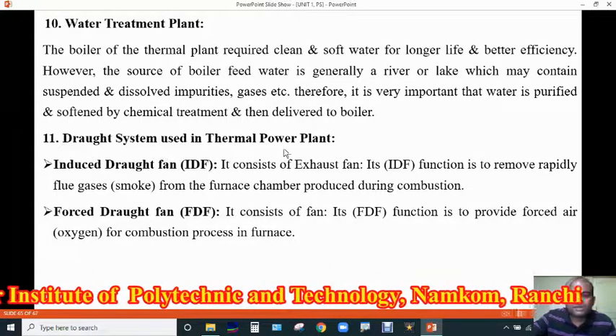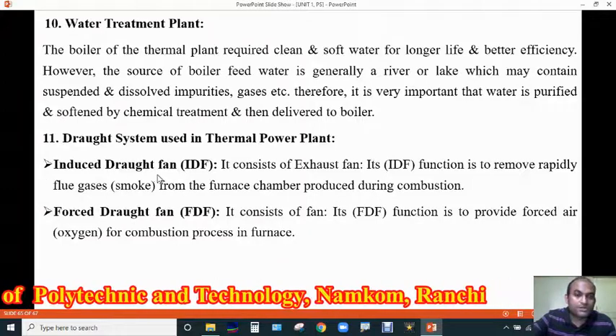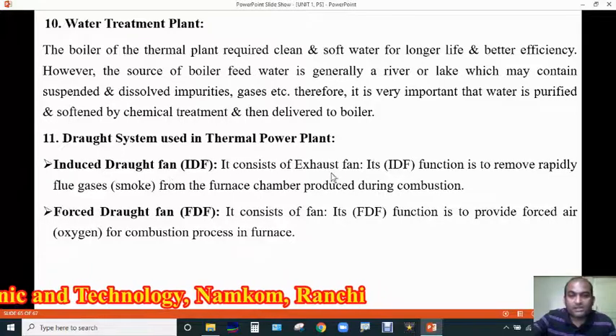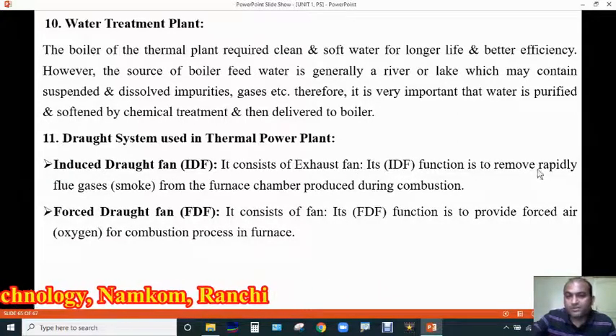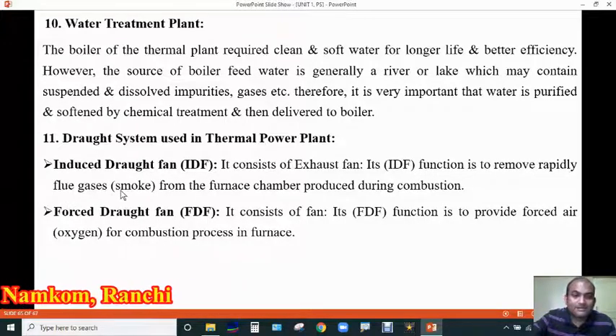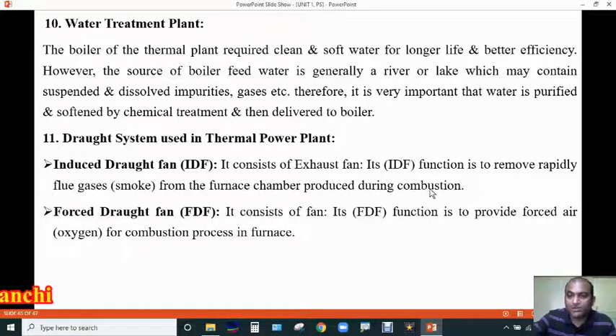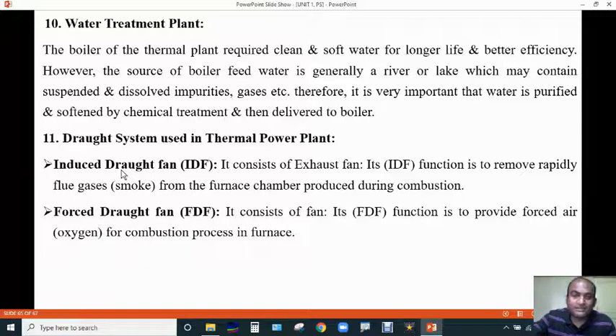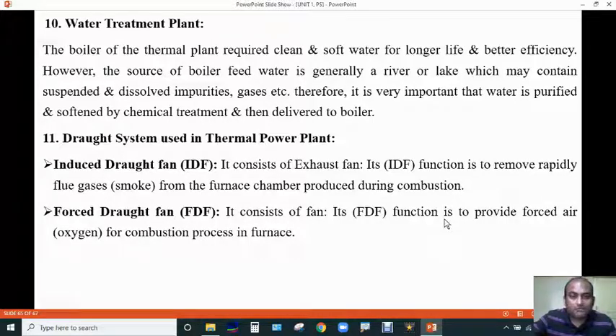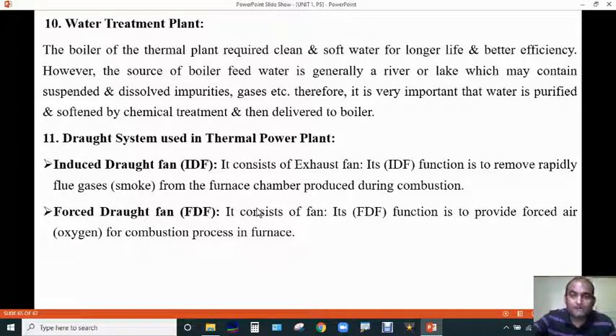The next section is the draught system used in thermal power plants. There are two draught systems: the induced draught fan and the forced draught fan. The induced draught fan is an exhaust fan whose function is to rapidly remove flue gases or smoke from the furnace chamber produced during combustion — it sucks gases from the furnace and sends them to the chimney. The forced draught fan provides forced air or oxygen for combustion in the furnace. It sucks air from the surrounding atmosphere and sends it to the furnace for the combustion of coal.